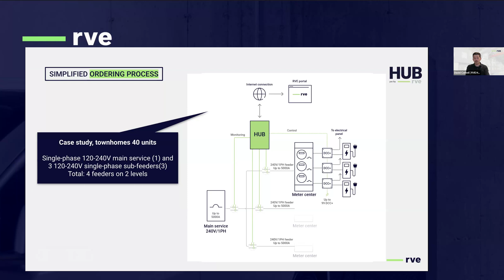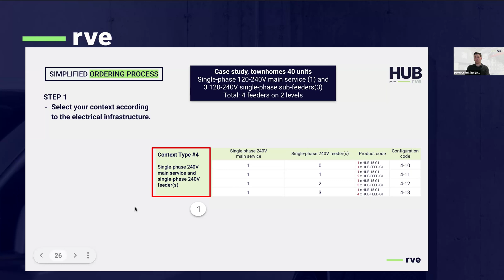To show you a typical installation scenario, here's a typical townhome or row home, a 40-unit building where the main feed is a 120 volt main service, and we have 3 single-phase sub-feeders feeding the meters going to each unit. In this case, the context we'd be looking at is context 4, which is a single-phase 240 volt main service.